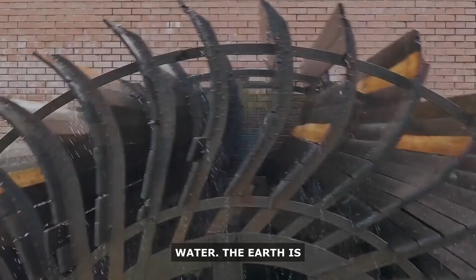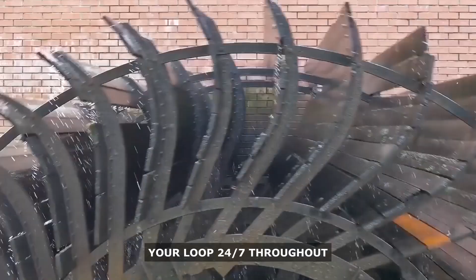Your ground temperature at 4 feet is relatively stable, but not absolutely static. In summer, the soil gets incrementally warmer because you're continuously extracting cool water and replacing it with slightly warmer water. The earth is absorbing heat from your system. If you run your loop 24/7 throughout July and August, by late August the soil has absorbed enough heat that your ground loop is no longer as effective.